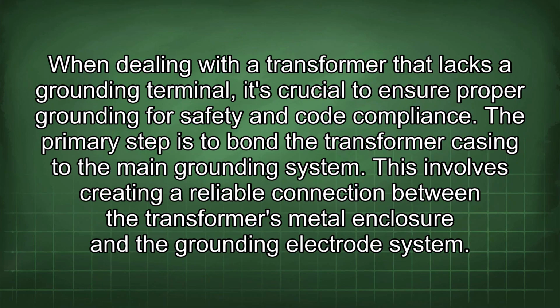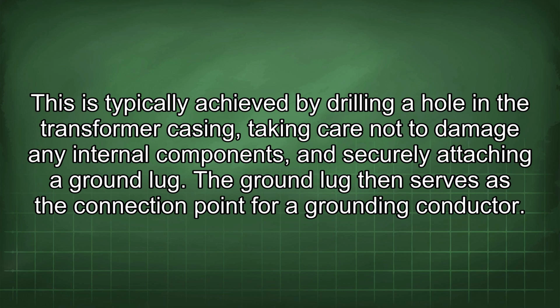When dealing with a transformer that lacks a grounding terminal, it's crucial to ensure proper grounding for safety and code compliance. The primary step is to bond the transformer casing to the main grounding system. This involves creating a reliable connection between the transformer's metal enclosure and the grounding electrode system. This is typically achieved by drilling a hole in the transformer casing, taking care not to damage any internal components, and securely attaching a ground lug.